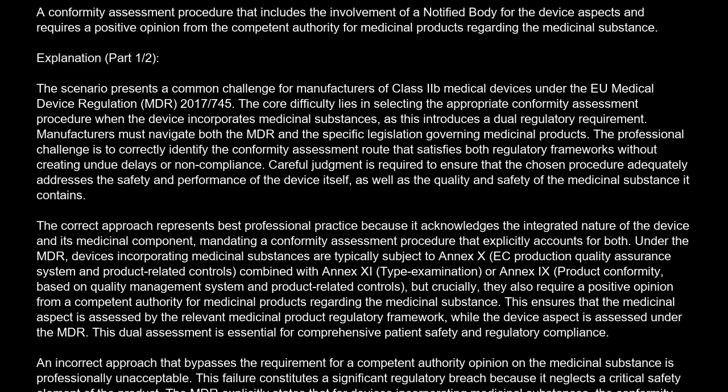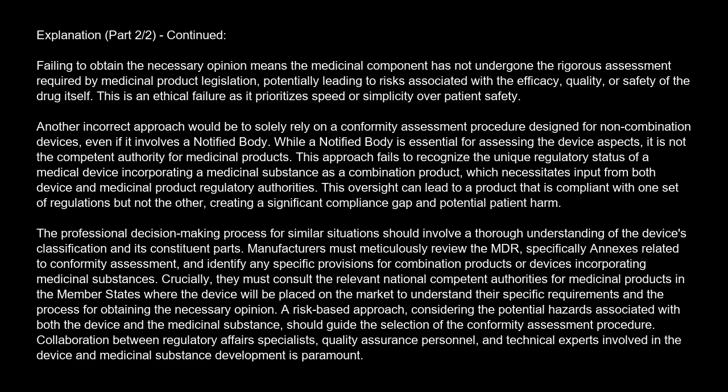An incorrect approach that bypasses the requirement for a competent authority opinion on the medicinal substance is professionally unacceptable. This failure constitutes a significant regulatory breach because it neglects a critical safety element of the product. The MDR explicitly states that for devices incorporating medicinal substances, the conformity assessment must take into account the medicinal substance. Failing to obtain the necessary opinion means the medicinal component has not undergone the rigorous assessment required by medicinal product legislation, potentially leading to risks associated with the efficacy, quality, or safety of the drug itself. This is an ethical failure as it prioritizes speed or simplicity over patient safety.